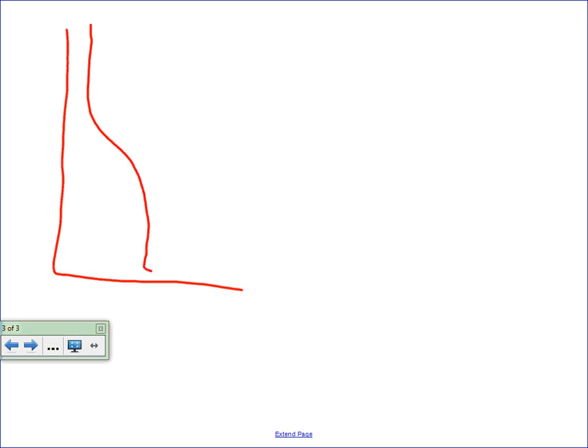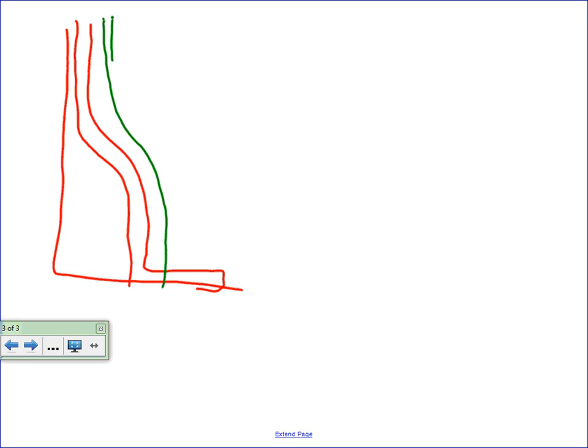So if you're looking at a TCC curve, time current characteristic curve, every breaker has a trip curve. And you guys are going to use SKM if you haven't already. Yeah, that's good. So all of a sudden you start picking breakers, and that 20 amp breaker may have a trip curve that looks like this. Now you got a 400 amp main breaker in that panel. Use different colors. Okay. So all of a sudden that 400 amp breaker has a curve that might look like that.